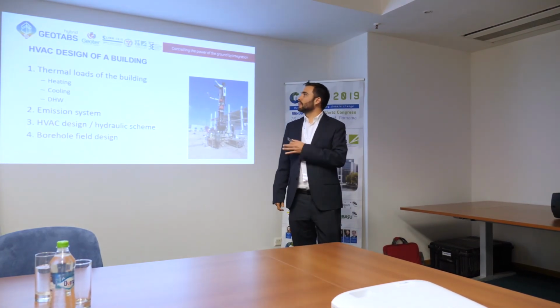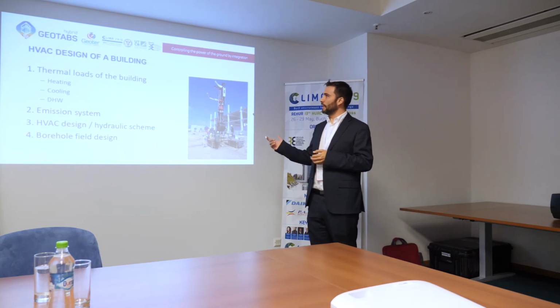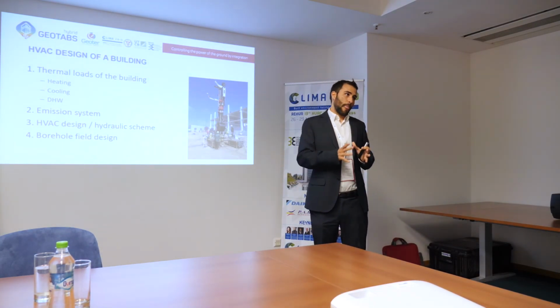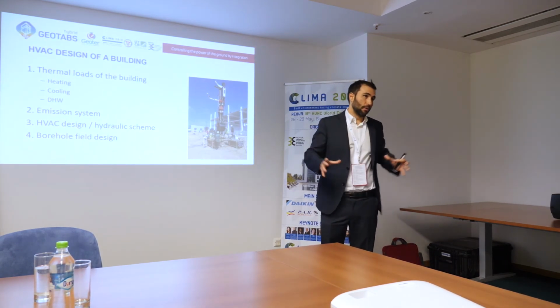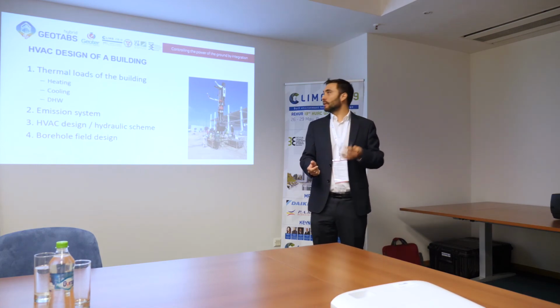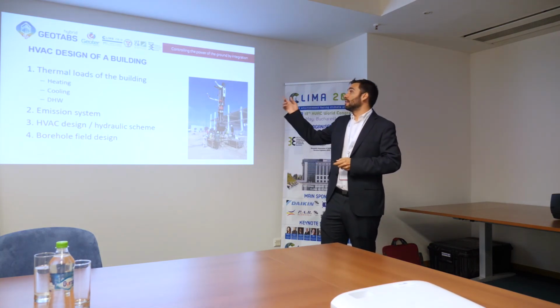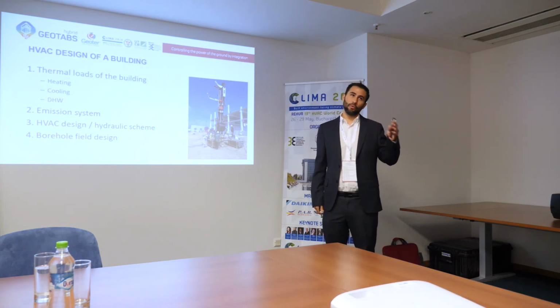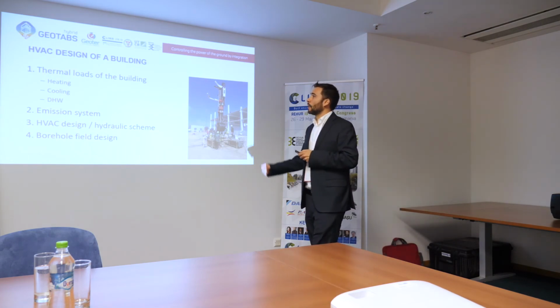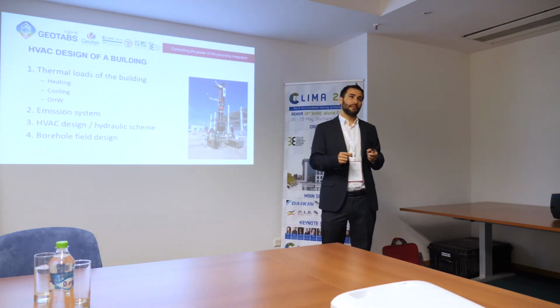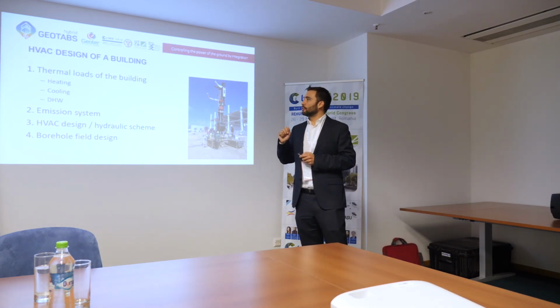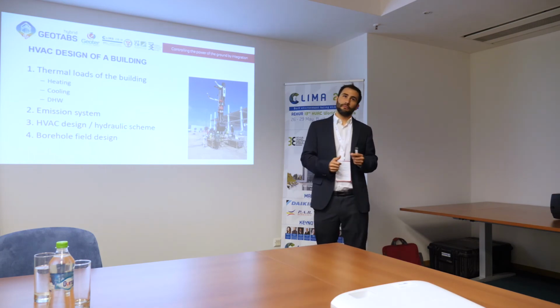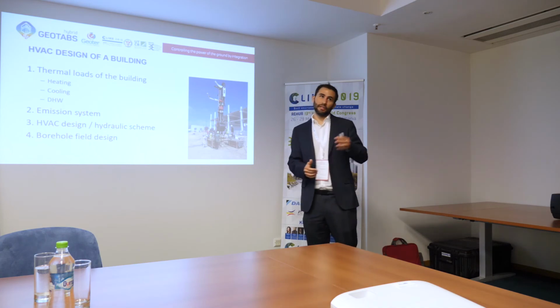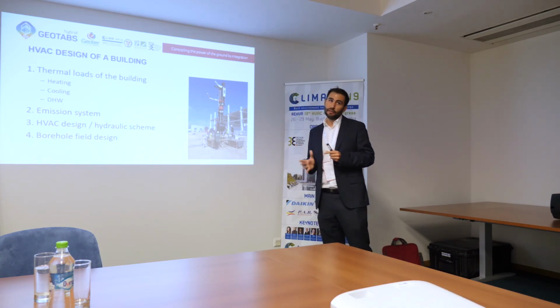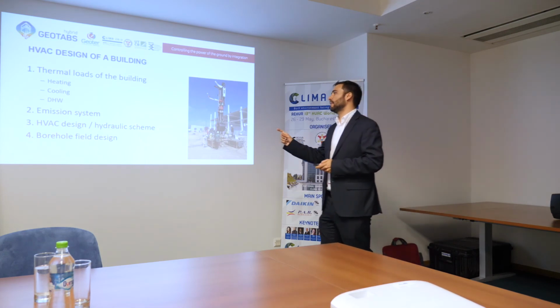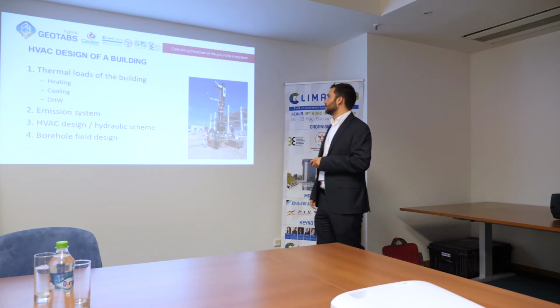So, when we talk about the design of a heating, ventilation, air conditioning system in a building, first of all, we have to analyze the envelope of the building, the use of the building, the occupancy, external gains, internal gains, bioclimatic aspects, and finally, we can calculate the heating, cooling, and domestic hot water thermal loads. With this information, and thinking about base load and peak load, we can choose the best emission system for our building and the best technical heating and ventilation design for our building. And finally, if we want to cover base load with geothermal energy, we can design the borehole field for the building.